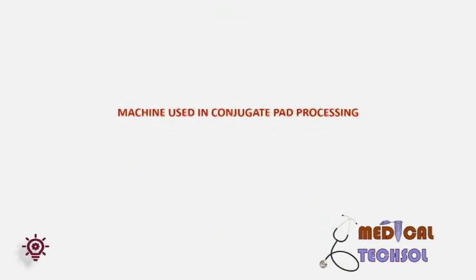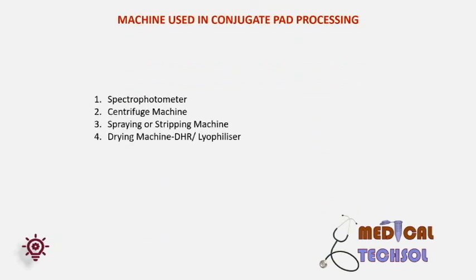Machines used in conjugate pad processing: 1. Spectrophotometer — used to scan the gold wavelength and determine the absorbance of the protein and gold conjugate. 2. Centrifuge machine — used to centrifuge the gold conjugate to collect the conjugated pellet. 3. Spraying or striping machine — used to dispense the gold conjugate onto the conjugate pad. 4. DHR or Lyophilizer — used for drying the conjugate pad.